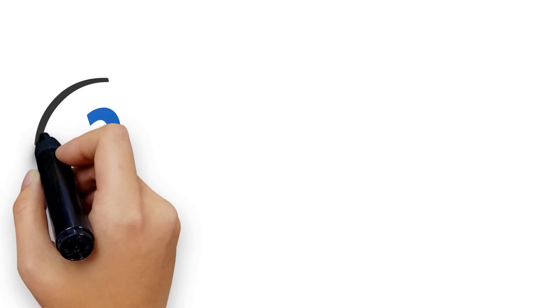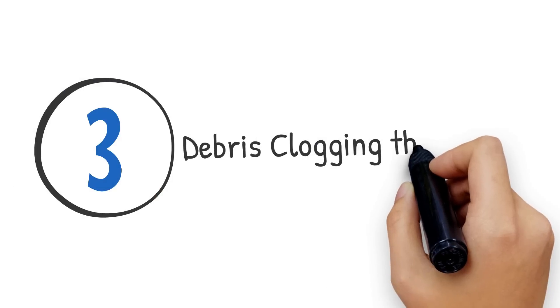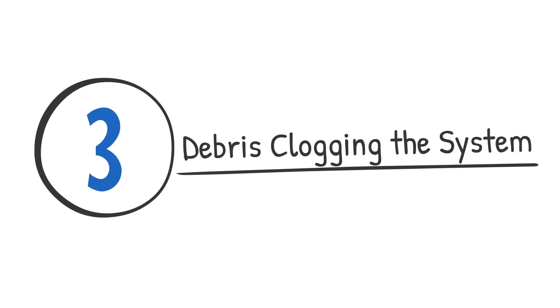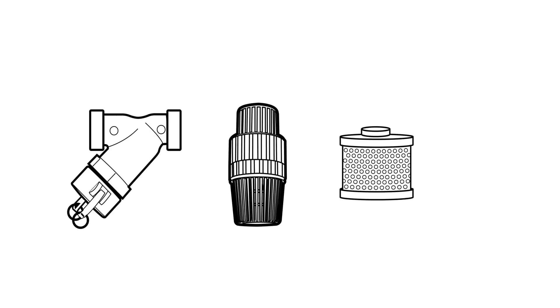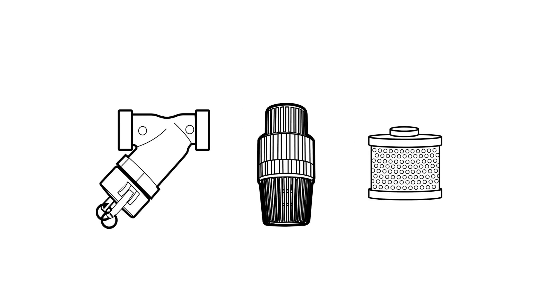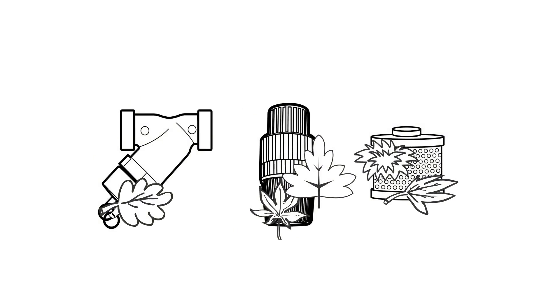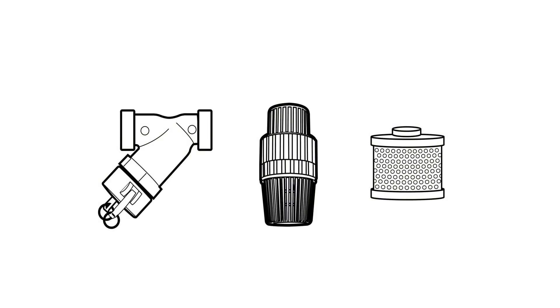And last but not least is debris in the system. If debris is caught in the intake filter foot valve and or the strainer, it will need to be removed and the part cleaned.